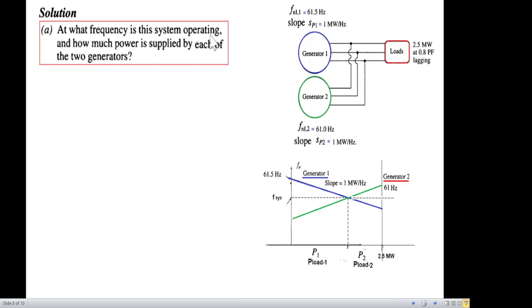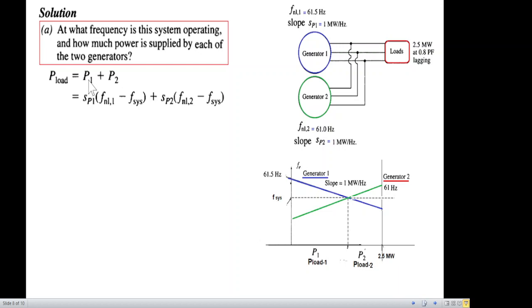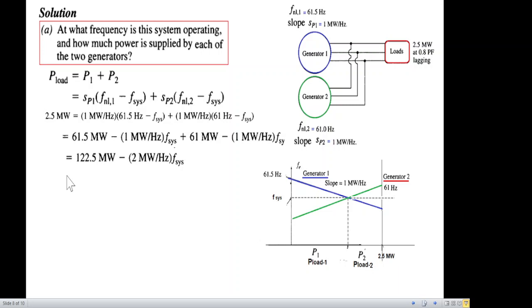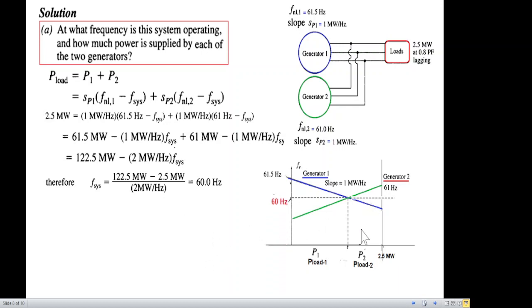Part A asks: at what frequency is the system operating, and how much power is supplied by each generator? We use the formula: P_load = P1 + P2. Plugging in the power formulas for P1 and P2 with the slope of 1 MW/Hz for both, a no-load frequency of 61.5 Hz for generator one and 61 Hz for generator two, and a total load of 2.5 MW, we solve and find the system frequency to be 60 Hz.